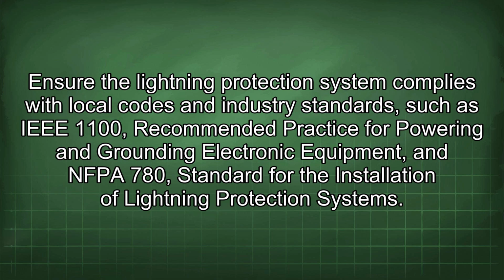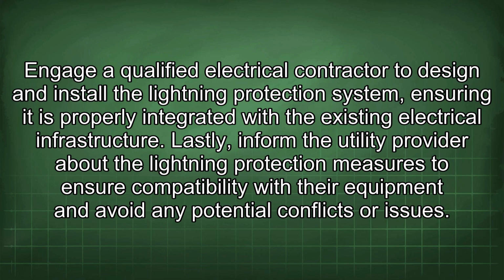Ensure the lightning protection system complies with local codes and industry standards such as IEEE 1100, recommended practice for powering and grounding electronic equipment, and NFPA 780, standard for the installation of lightning protection systems. Engage a qualified electrical contractor to design and install the lightning protection system, ensuring it is properly integrated with the existing electrical infrastructure. Lastly, inform the utility provider about the lightning protection measures to ensure compatibility with their equipment and avoid any potential conflicts or issues.